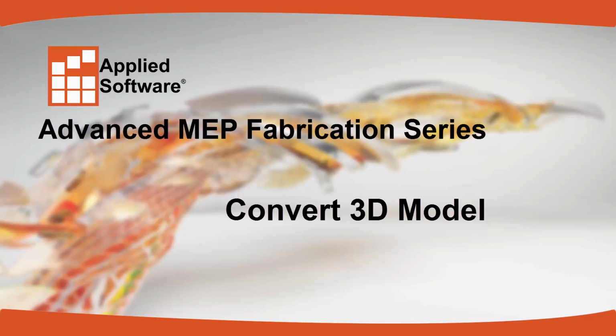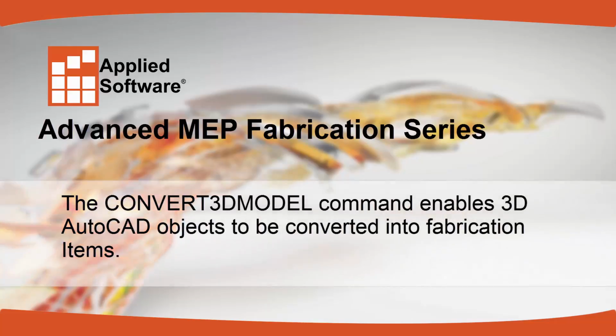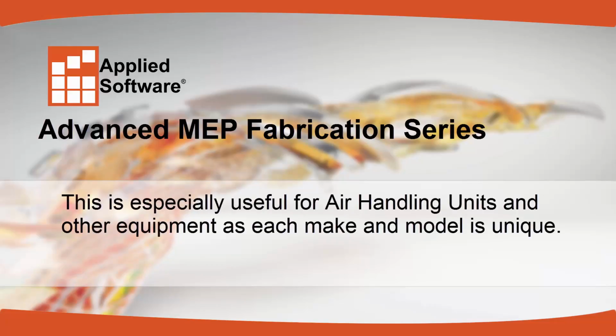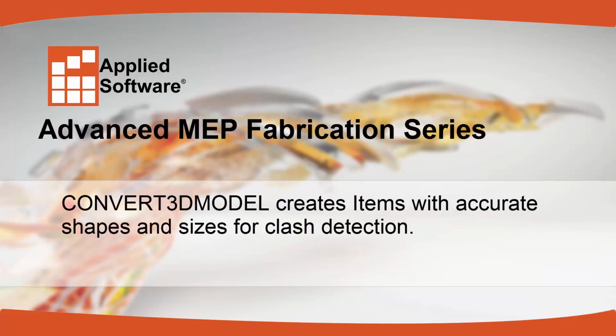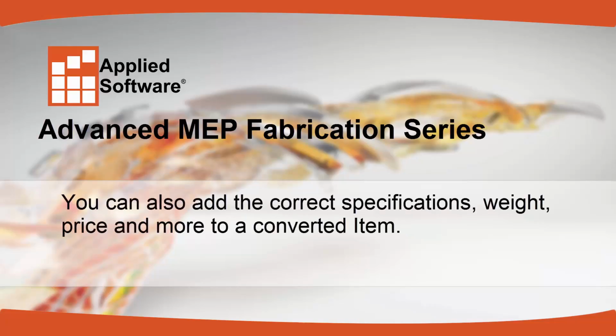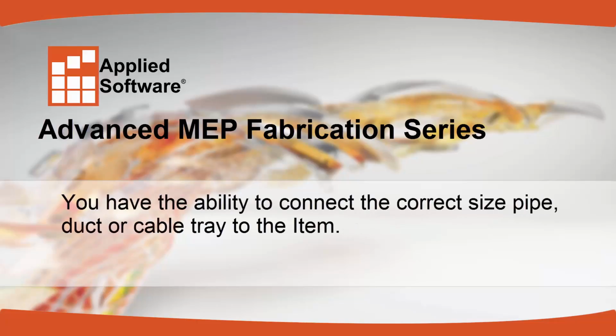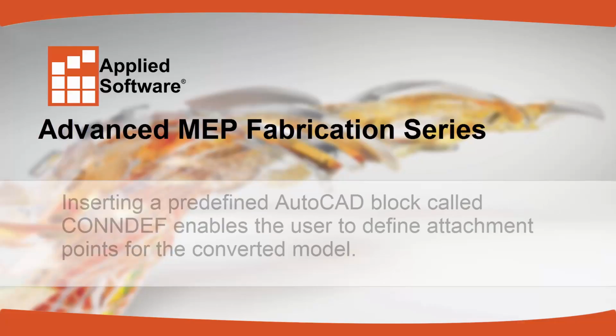Convert 3D Model. The Convert 3D Model command enables 3D AutoCAD objects to be converted into fabrication items. This is especially useful for air handling units and other equipment, as each make and model is unique. Convert 3D Model creates items with accurate shapes and sizes for clash detection. You can also add the correct specifications, weight, price, and more to a converted item. You have the ability to connect the correct size pipe, duct, or cable tray to the item.